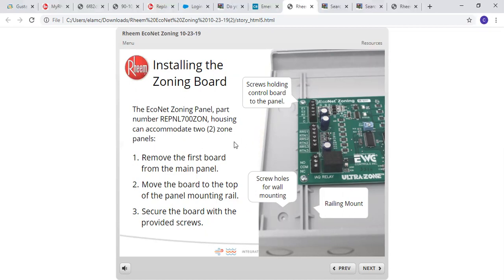Installing the board. There again, the part number is the REPNL 700 ZON. The housing itself can accommodate 2 zone boards. If you have to add boards, so if you're doing 3 or more, you remove these screws. There's 4 screws on each side on the outer edges. Remove those, and then you can move your board up, reinstall the screws on all 4 corners, and then you can mount your new board accordingly. So the top board will be zones 1, 2, and 3, and below would be 3, 4, 5, and 6, or however you're going to do that.